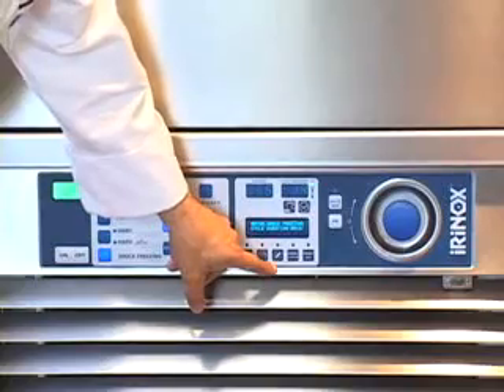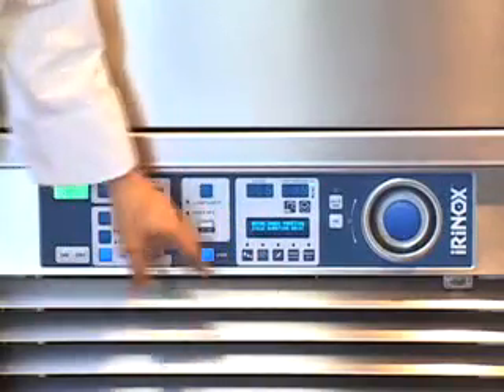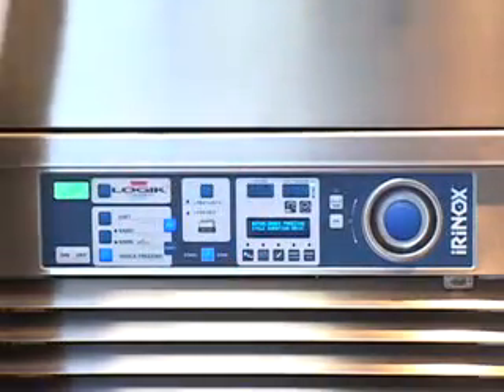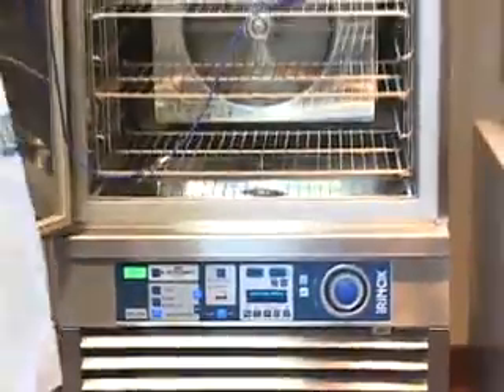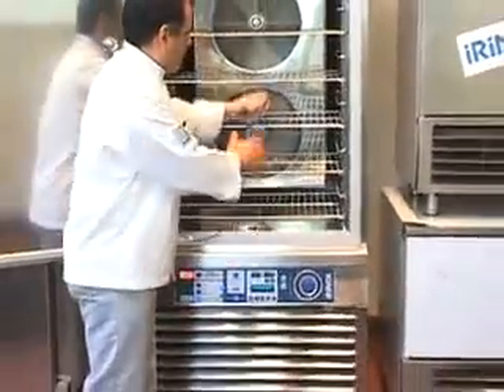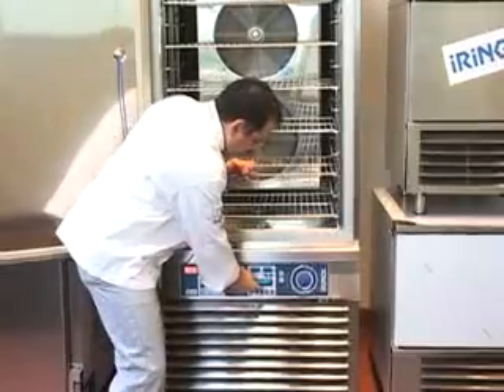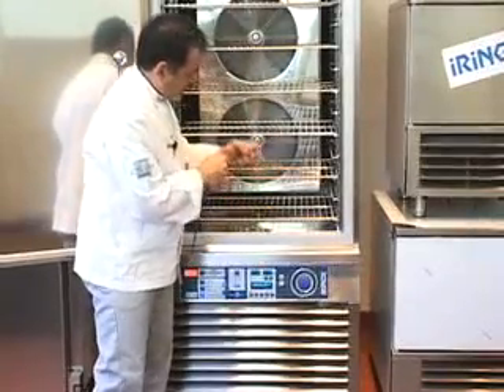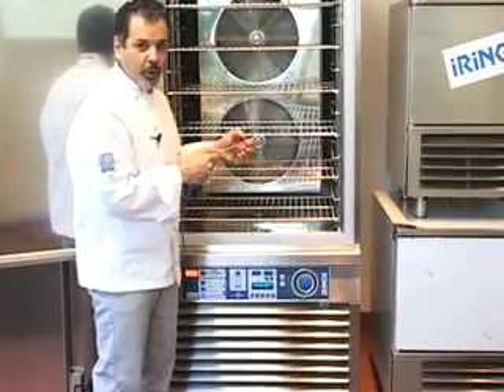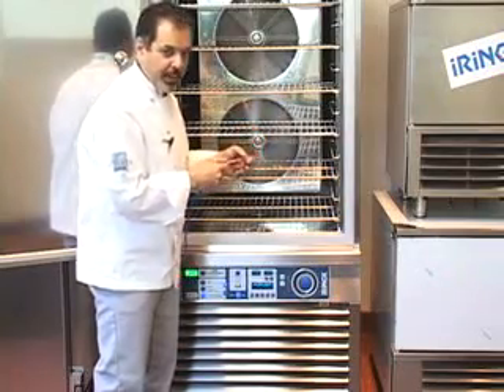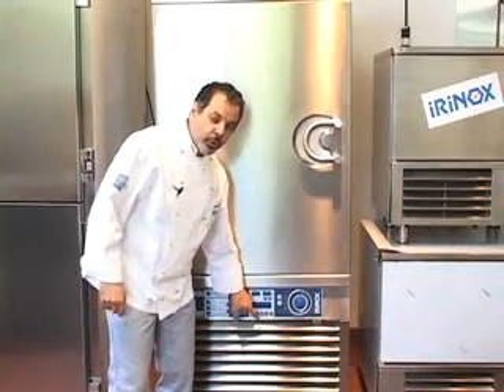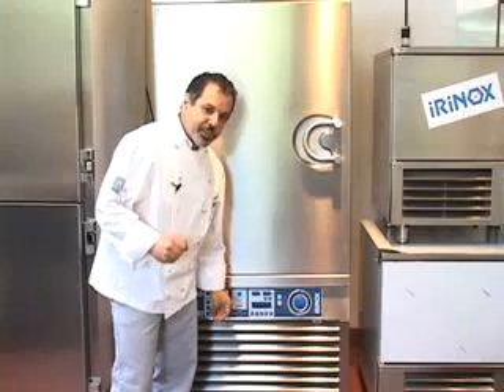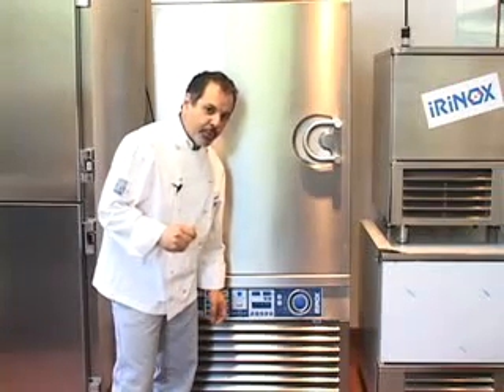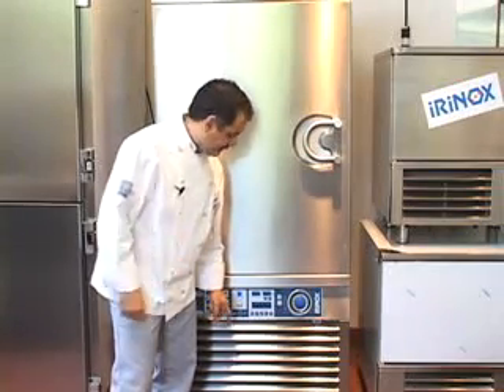I now demonstrate the probe heat. If I'm at the end of a shock freeze mode, and here I'm just demonstrating with an apple, and the probe is frozen in the apple, I simply hit the probe heat button, and after a few seconds it'll allow me to remove the probe from the product without damaging the product. Remember that the probe heat will only work upon the completion of a shock freeze mode, and that the probe senses that it is below 0 degrees.